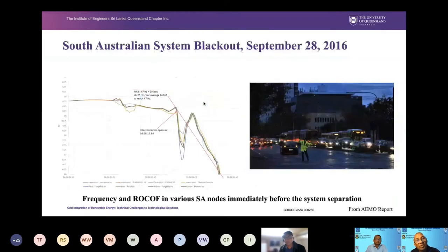So this slide shows the ROCOF, the so-called ROCOF. ROCOF means rate of change of frequency. There are relays put in place. ROCOF relays are usually set at 0.5 hertz per second. If anything goes beyond that, the relays are going to trip different loads and generation to protect the rest of the system. So here we can see the ROCOF was very significant.